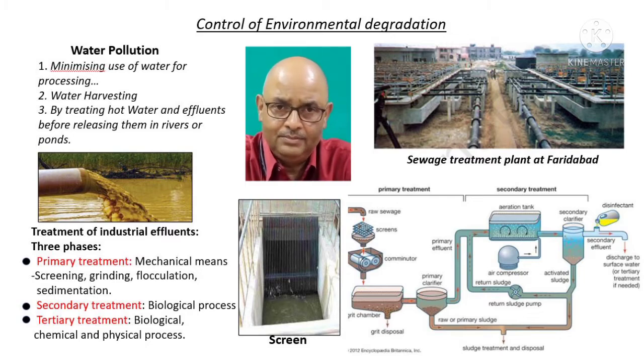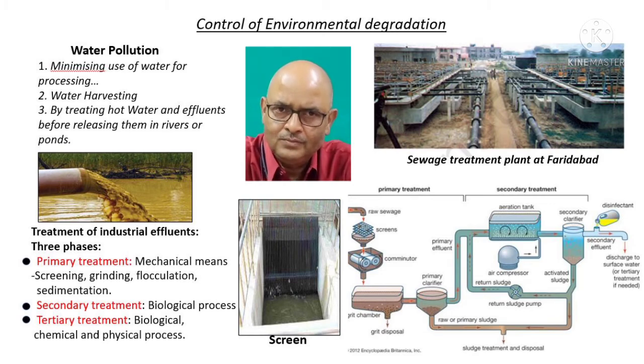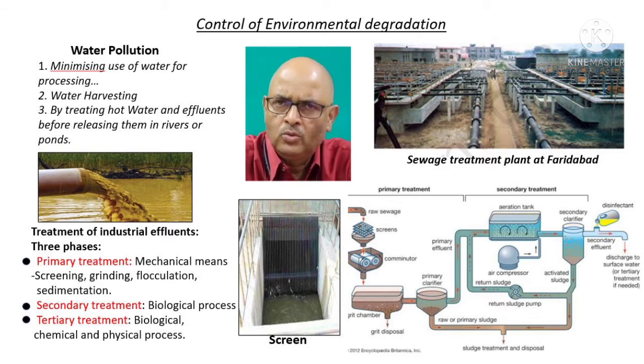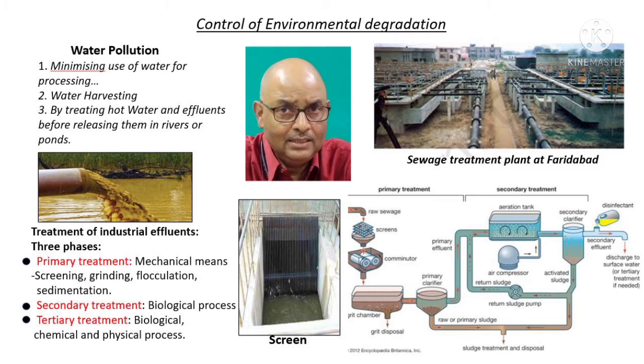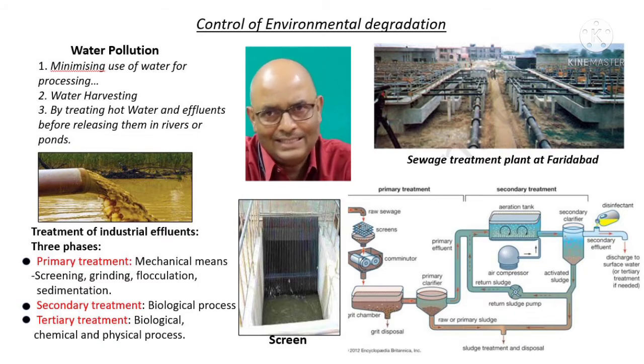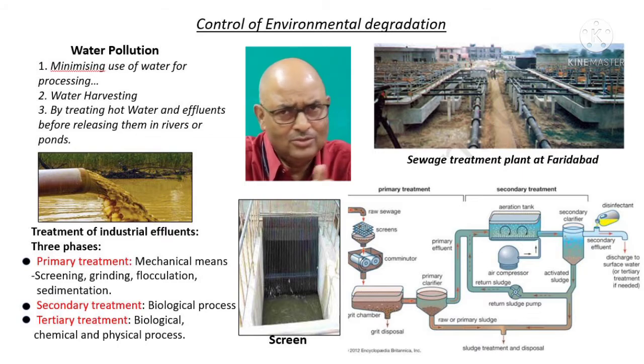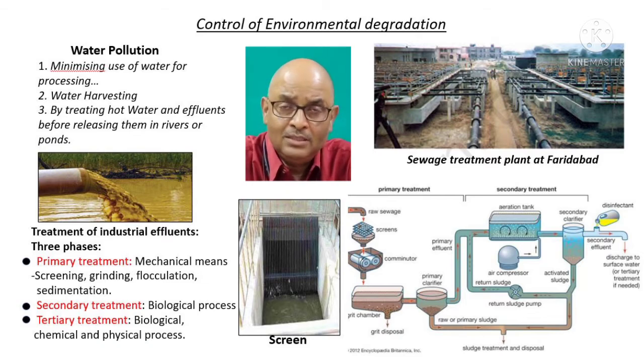Primary treatment is done by mechanical means. It involves screening, grinding, flocculation, and sedimentation. By screening, we prevent coarse solids such as plastics, rags, and other trash from entering the treatment plant. As you can see in the slide, solids get trapped by inclined screens or bar racks. Just imagine how you filter tea before pouring it into the cup - screening is a sort of filtering.